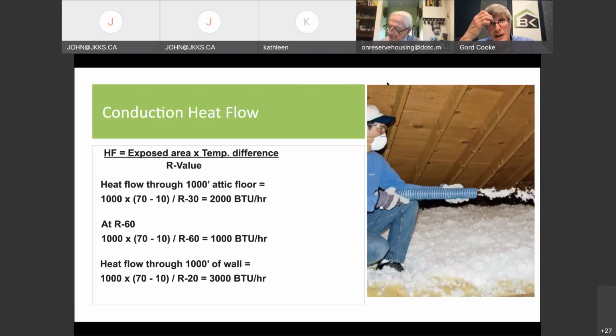And for those who aren't familiar with that term, we did that, I think, in the last session in building science, that when we say your wall's insulated to R20, we know the cavities are insulated to R20, but every 16 inches on center, you have a piece of wood, and that piece of wood is only R5. So I have to take the weighted average of that wall. That's called the effective R value. So just for example, for Dave's benefit, the effective R value of a standard 2x6 wall is not R20, it's R15. So if I plug in R15, 1,000 times 60 divided by 15, my new heat flow would be 4,000 BTUs. So good catch, Dave. The actual heat flow through that wall is not 3,000 BTUs, it's 4,000 BTUs.